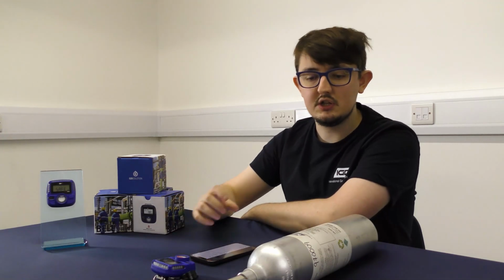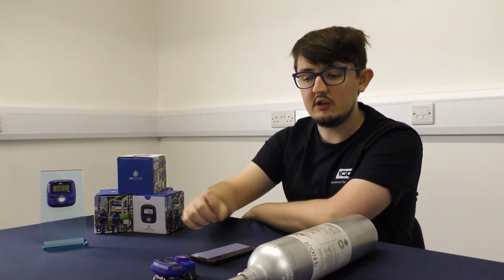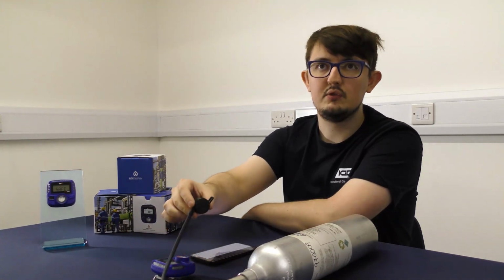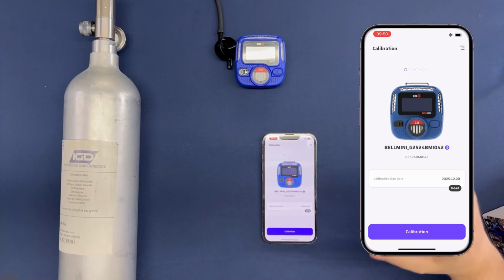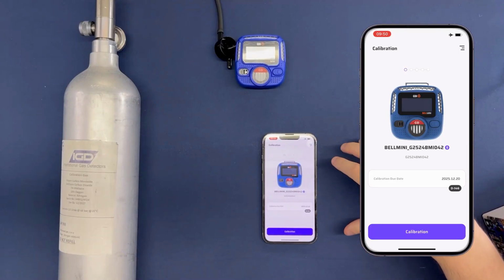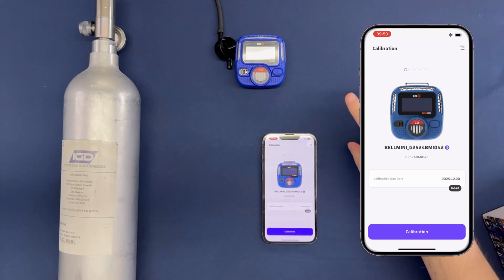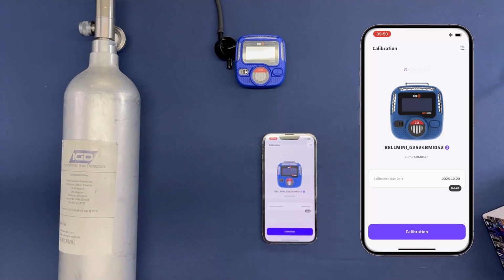And for the calibration, you'll need a gas bottle that matches the sensor type that you've got. You'll need a regulator, and you'll need your Cal adapter from the BELLMINI. So as you can see, we've now accessed the calibration section. And before we press calibration, you just got to make sure that you have your BELLMINI with you, you've got the Cal adapter, your gas bottle that matches the sensor type, as well as the regulator.